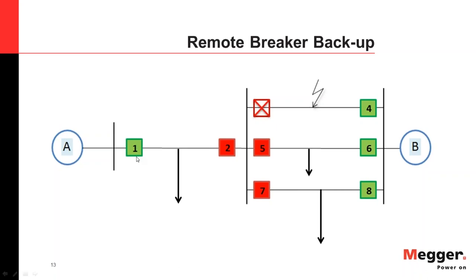The first disadvantage is that the strength of sources might lead to an underreach. For example, if source A is weak and cannot sense the fault between Breaker 3 and Breaker 4, it will not trip even after the coordination delay. The second disadvantage is coordination delay — it may be too long before the relay at Breaker 1 decides to trip, and for a serious fault this could destabilize the grid.